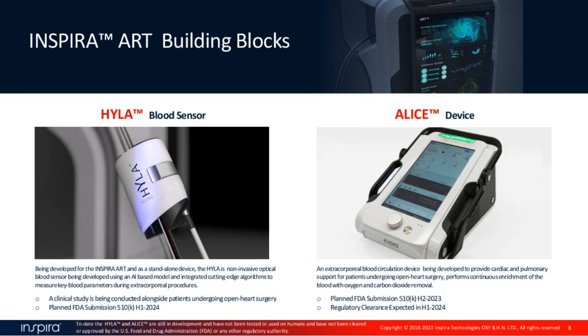And what it uses is an optical sensor with an AI-based model and algorithms. It's non-invasive. In other words, there's no physical contact between the sensor and the blood. And it's basically looking at the digital images of the blood passing through the tube and converting that information to key blood parameters. What does that mean? Potentially, we would be able to say, okay, we know what the saturation level of the patient's blood is at every given time, continuously, in real time, without taking a drop of blood, for example. And if you can do that, you can use the blood sensor to see what's happening with the patient. In other words, if all of a sudden he's deteriorating, something's happening to the patient's key parameters, we would know about it and inform the medical team.